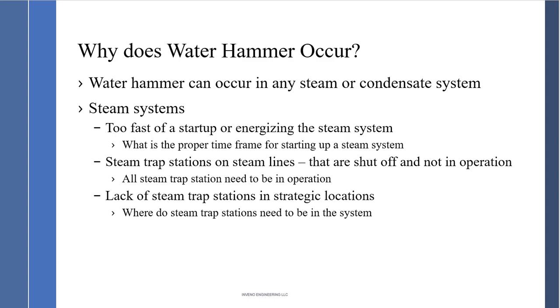Steam trap stations on steam lines that are shut off are not in operation. This is a very unsafe practice. All steam trap stations need to be in operation. No matter how well we insulate the steam lines, condensate is going to occur. We have to remove the condensate out of the steam system to prevent Waterhammer. The next thing is lack of steam trap stations in strategic locations. Where do we need steam trap stations in the system? So the system design has to place the steam trap stations in strategic locations to ensure that we get the condensate out and that we don't have buildup and we don't have Waterhammer.